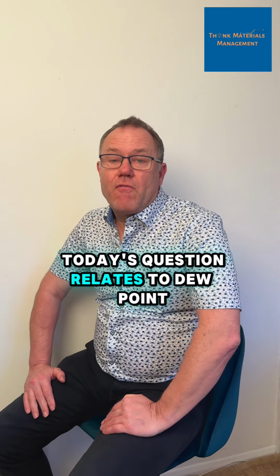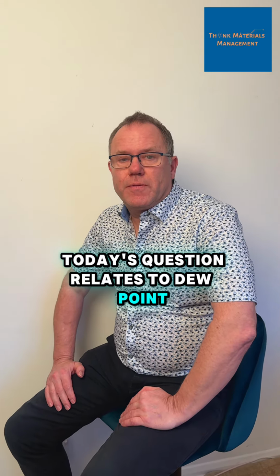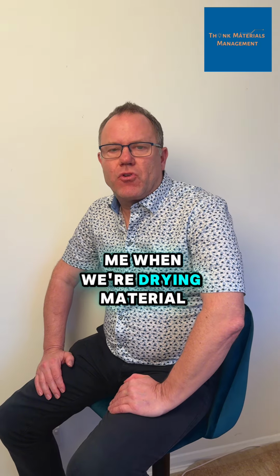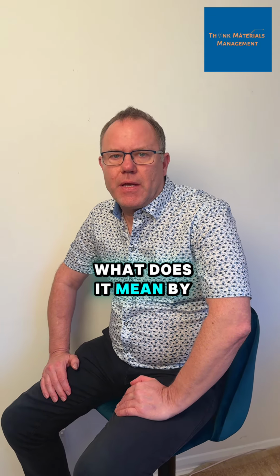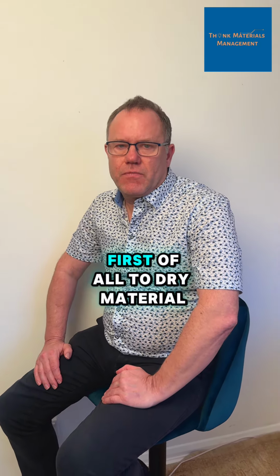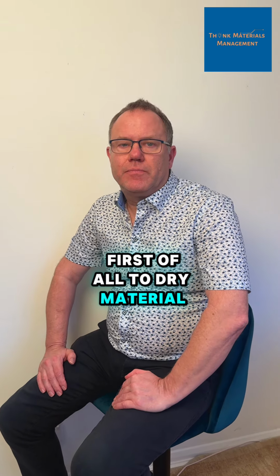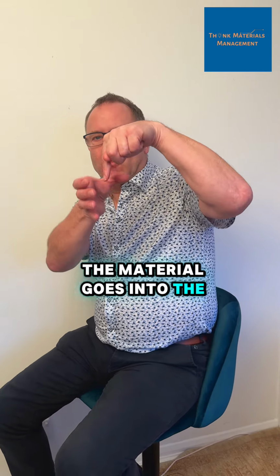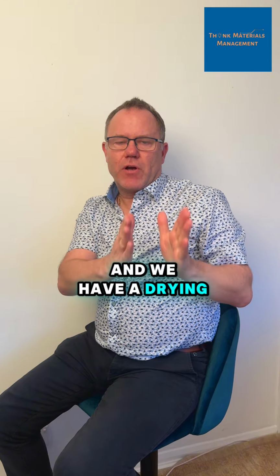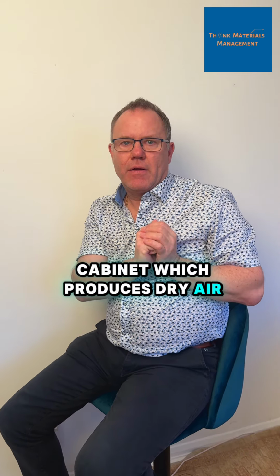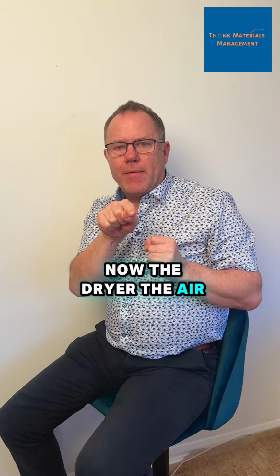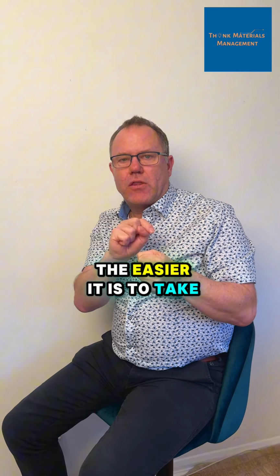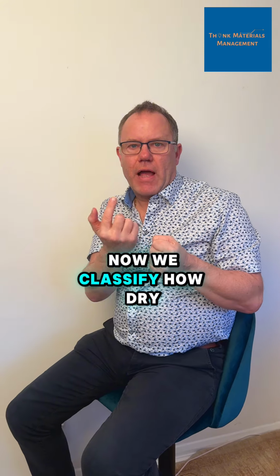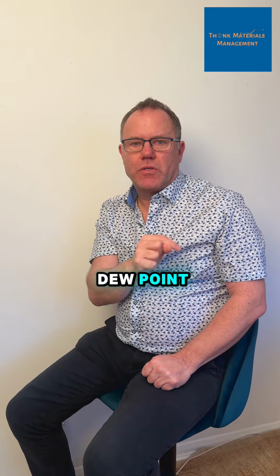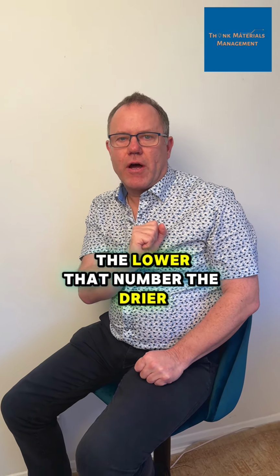Today's question relates to dew point. A lot of people ask me, when we're drying material, what does it mean by dew point? First of all, to dry material, the material goes into the drying hopper and we have a drying cabinet which produces dry air. Now, the drier the air, the easier it is to take the moisture out of the material. We classify how dry the air is by the dew point. The lower that number, the drier the air.